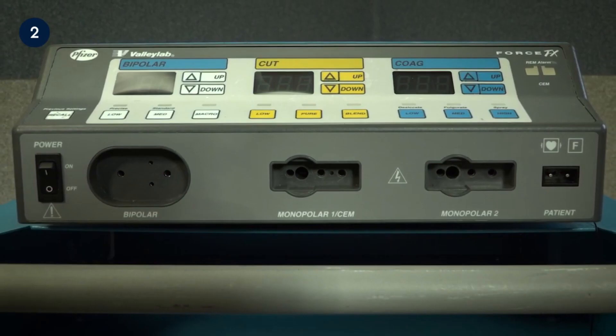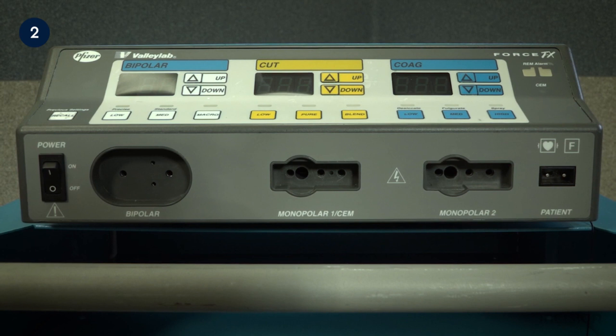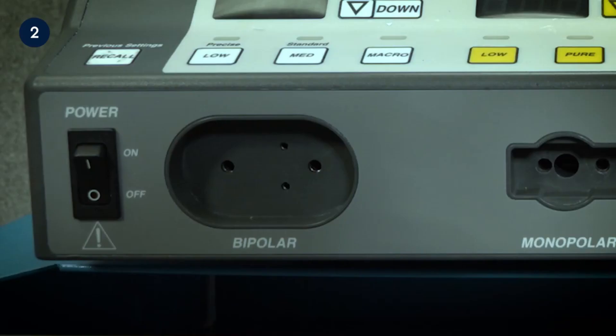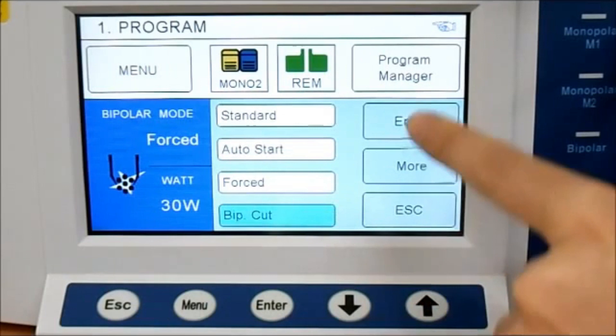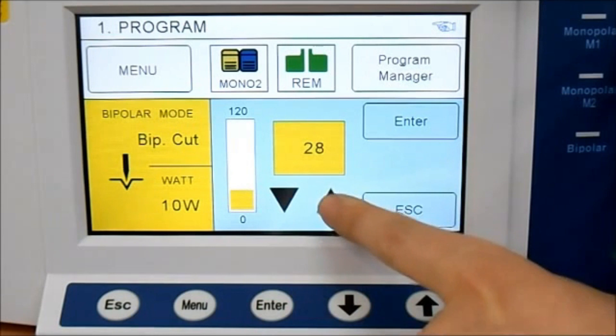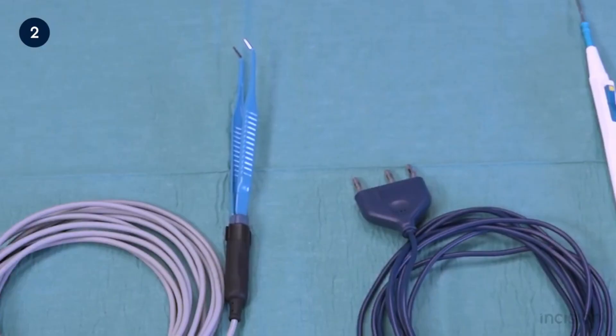Let's begin with bipolar electrosurgery. In bipolar electrosurgery, both the active electrode and return electrode functions are performed at the site of surgery. The two tips of the forceps perform the active and return electrode functions. Only the tissue grasped in the forceps is included in the electrical circuit. Because the return function is performed by one tip of the forceps, no patient return electrode is needed. Bipolar electrosurgery operates regardless of the medium in which it is used, permitting coagulation in a fluid environment — a great advantage in a wet field. As a result, bipolar electrosurgery is often referred to as wet field cautery.